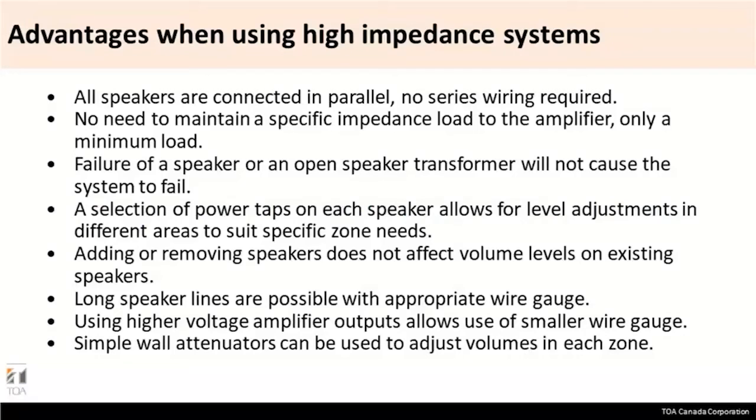All right, and again, you could tap these speakers at different tappings as long as you are within the range of the amplifier. A selection of power taps on each speaker allows for level adjustments in different areas. So it could be an outdoor parking lot in a school where you need horn speakers. Let's say they are tapped at 15 watts, and the corridor speakers that I just spoke about are tapped at 1 watt. So they're going to be 5 watts in total, 1 watt into five speakers, and you might have, let's say, three horn speakers, 15 watts each outside in the parking lot, and that could be around 45 watts.